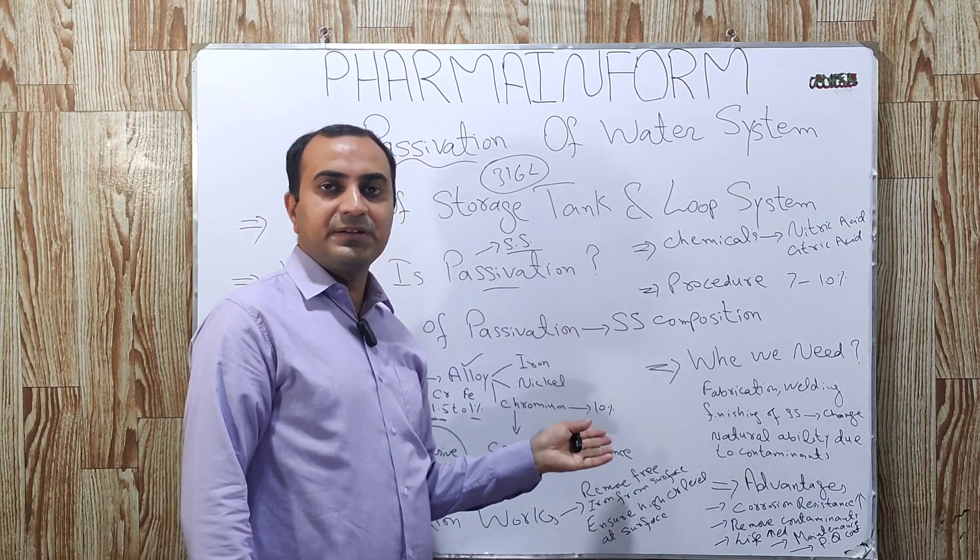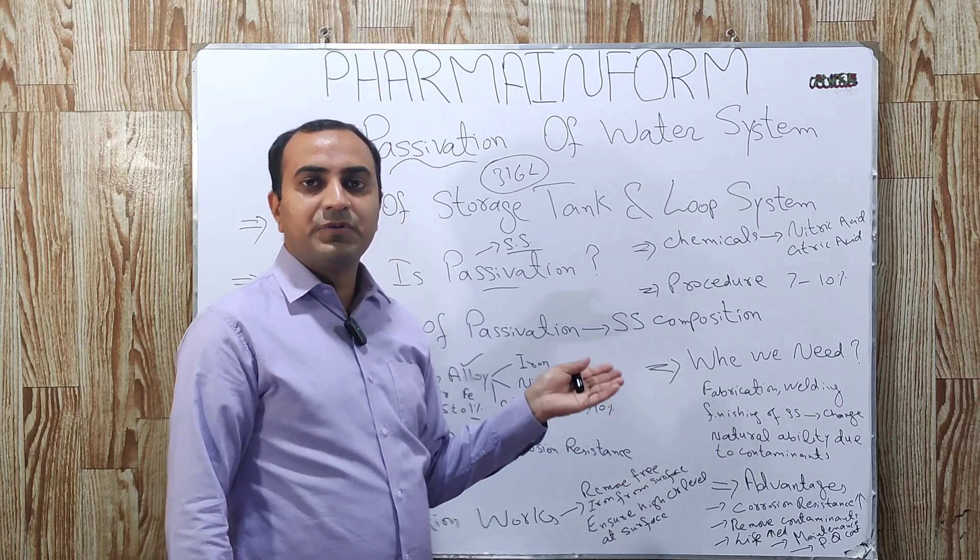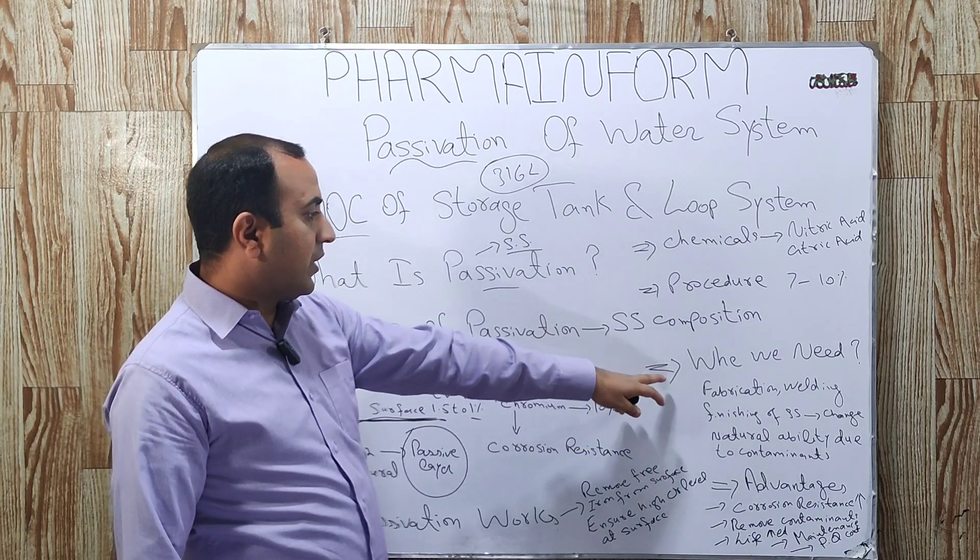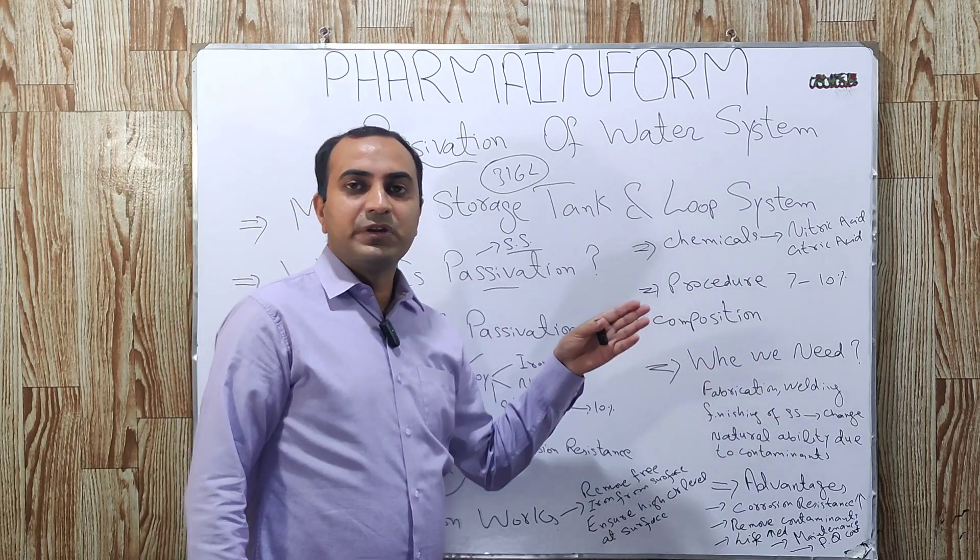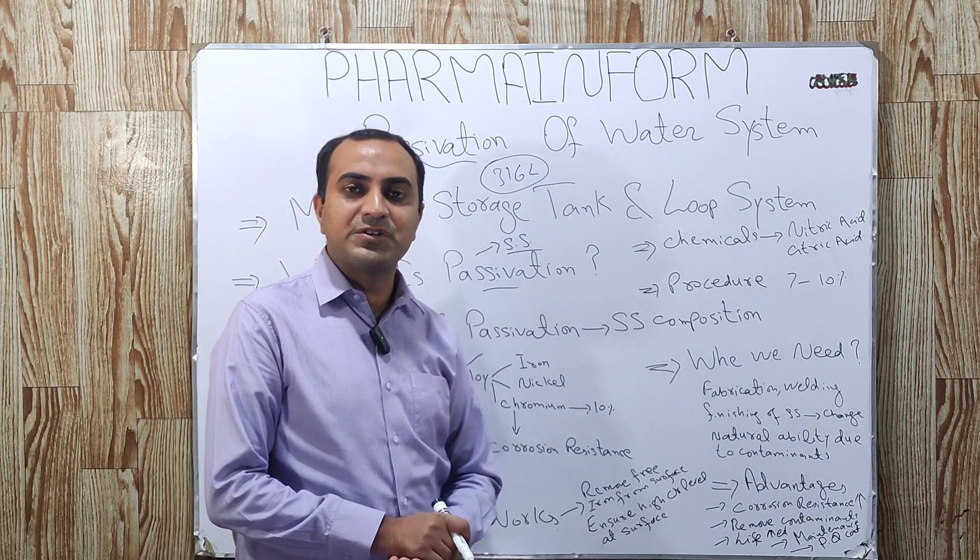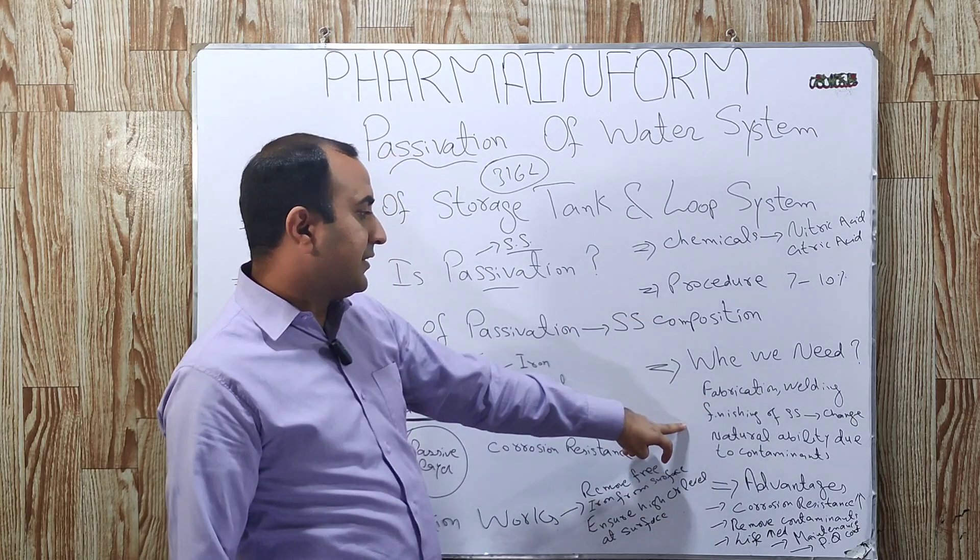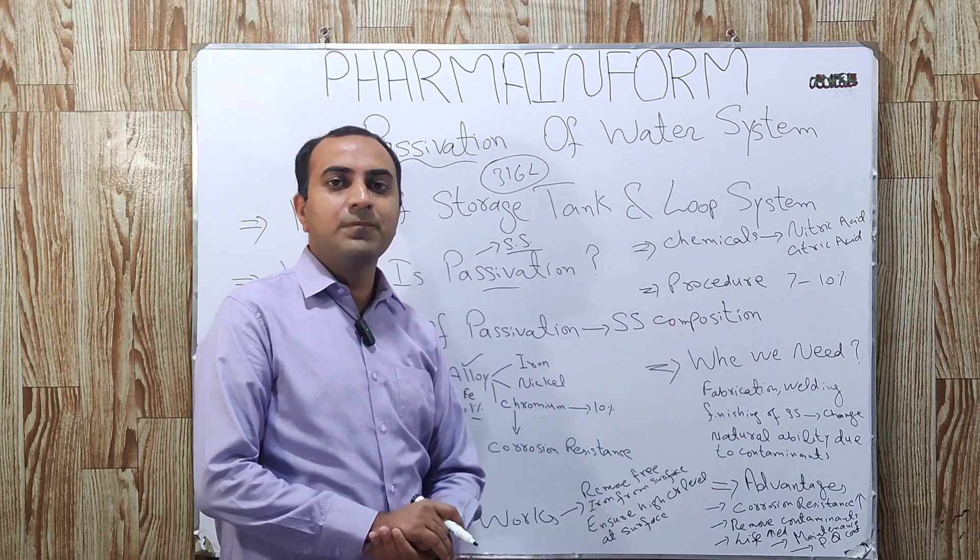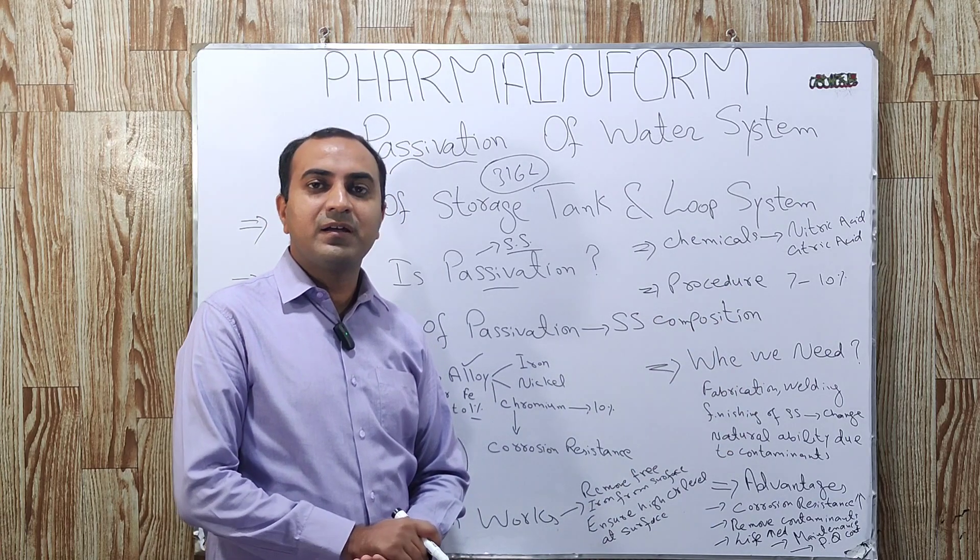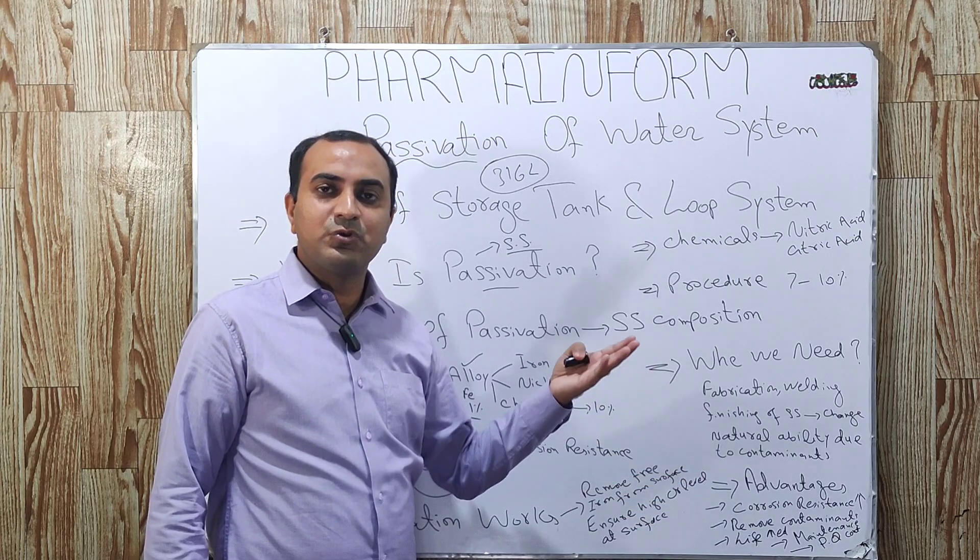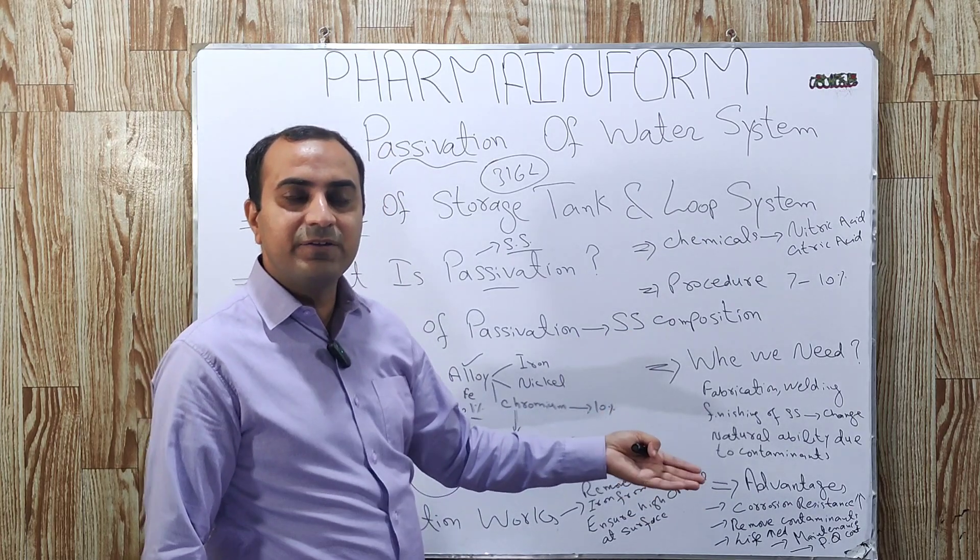When we need passivation? As we discussed that, naturally there exists a layer which is known as passive layer for corrosion resistance. But why we need passivation? We need passivation whenever we do any modification or fabrication or finishing to the stainless steel or there is any welding to the stainless steel. We know that there may be many joints for the loop system and we use welding. Orbital welding is used.